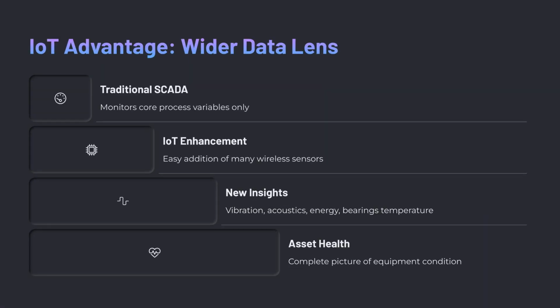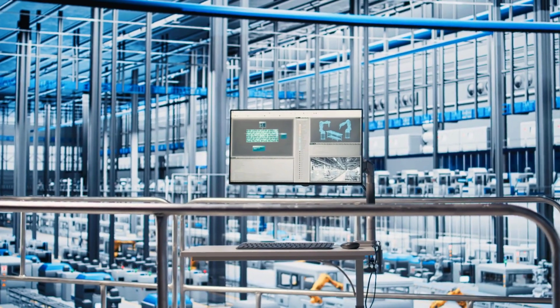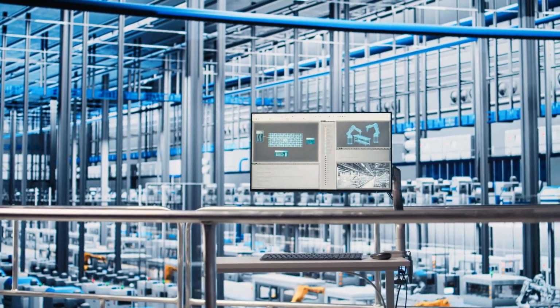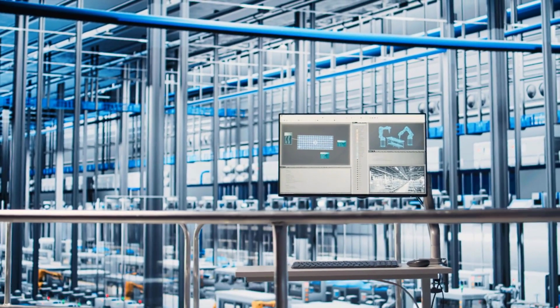Wider data lens. SCADA typically monitors core process variables. IIoT lets you easily add tons of other sensors: wireless vibration on pumps, temperature on remote bearings, energy consumption on individual machines, acoustic sensors listening for leaks. Things that were too expensive or complex to wire back before. Suddenly, you see so much more about your asset health.